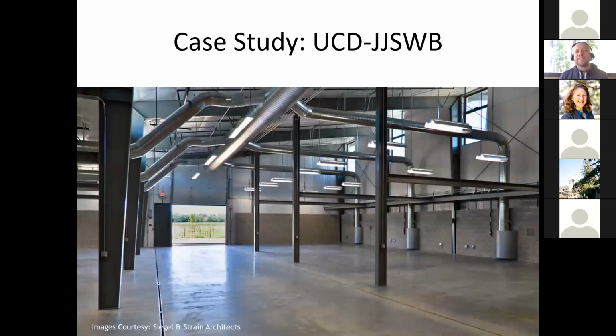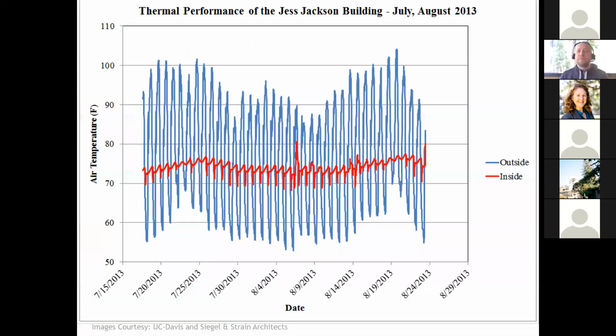Here's a shot of the inside, so you can see that ductwork as it comes down to the side of the building, landing at the floor as very low velocity displacement diffusers. The idea is we use outside air at night to cool all of that mass, and then through the day it can just ride out. It's very effective at keeping the temperature really steady.